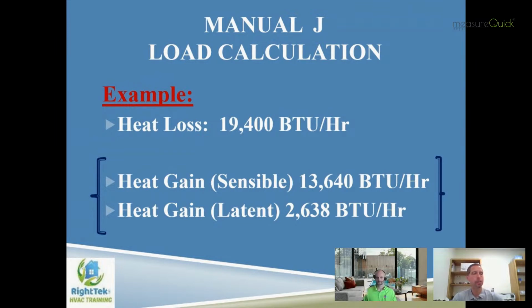So all that being said, let me walk through how we would do things now, if we follow the current Manual S, which is still an option. In the new Manual S, we call it the simplified heat pump sizing method, and it's similar to what many of you as practitioners are probably already familiar with. I pulled some numbers from a load calc that I've done, and what you see on the screen here is a home with a heat loss of about 19,400 BTUs per hour. You can also see our sensible and latent breakdown there.